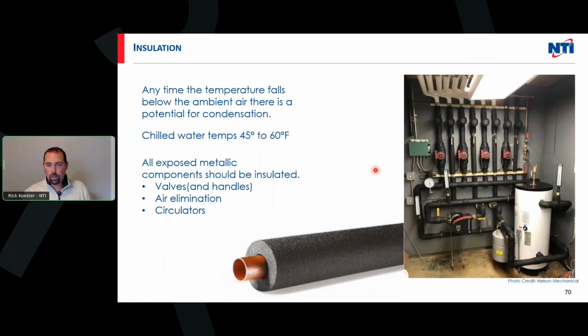Insulation, as I just mentioned, is a huge topic as well, especially if we're dealing with chilled water applications. The first time somebody deals with it, I'm going to tell you right now, they do not insulate it properly. If they've done chilled water applications, they understand that every single metallic part of the system is going to sweat. If the dew point is right in that mechanical room, every ball valve, circulator, air vent, air separator, magnetic filter, anything that has water going through it at 45 to 60 degrees, is going to sweat.